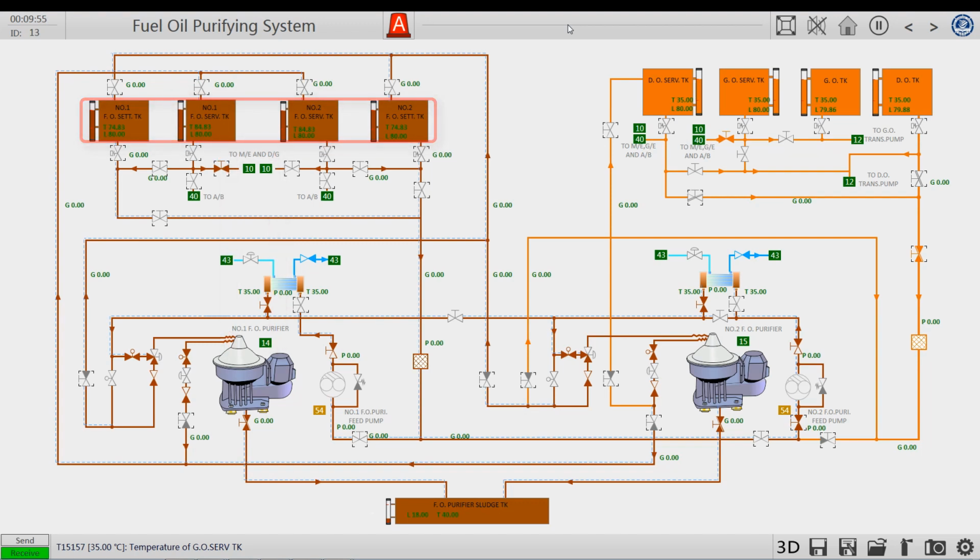So the 4 heavy oil tanks have valves to the oil separator, and they are fast closing valves. Fuel goes through the inlet filter, the oil separator supply pump, and the oil separator heater, then through this line into the oil separator. This is the inlet side of the oil separator. The fuel oil is centrifuged and purified in the oil separator. The clean fuel is transported to the service tanks by the clean oil outlet. The bypass fuel is recycled back to the settling tank from the line below.